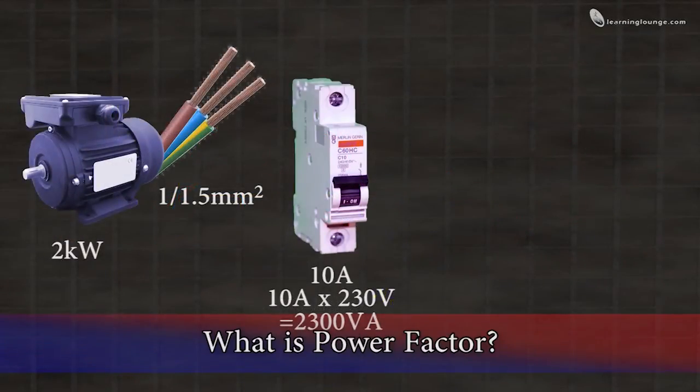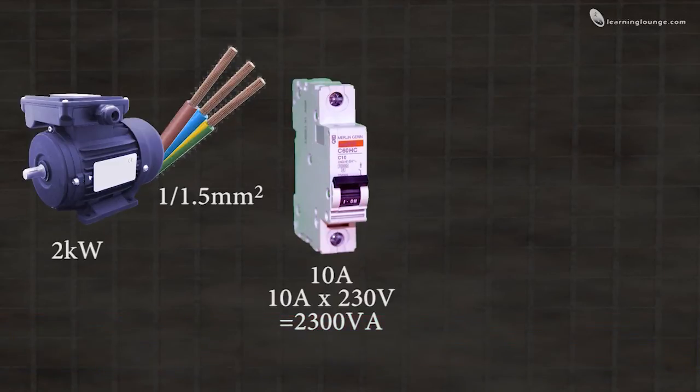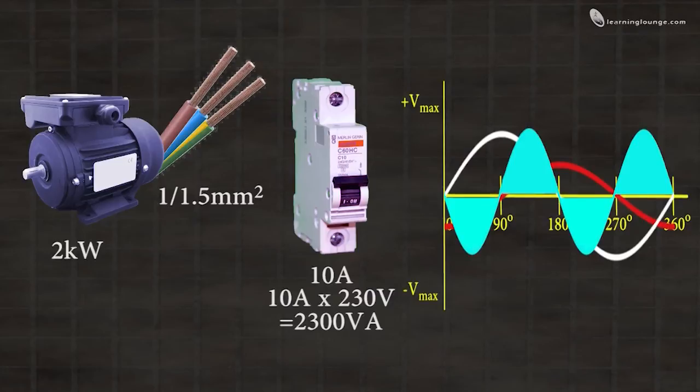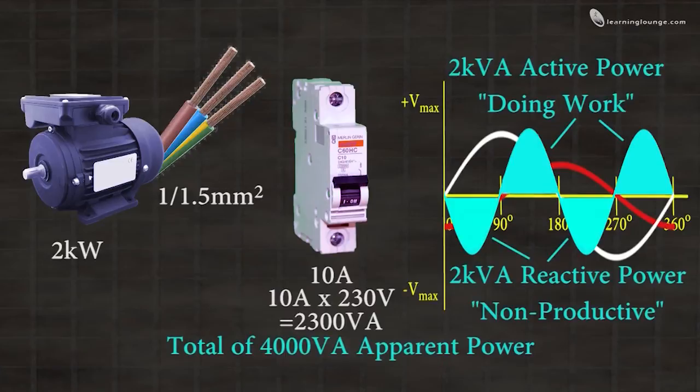So on paper so far, our 2300 VA can accommodate our 2000 watts of power. However, if we consider power factor and the fictional example of a purely inductive load, this motor could in theory have up to another 2000 volt amps flowing at the same time, which will well exceed the ratings of both cable and circuit breaker.